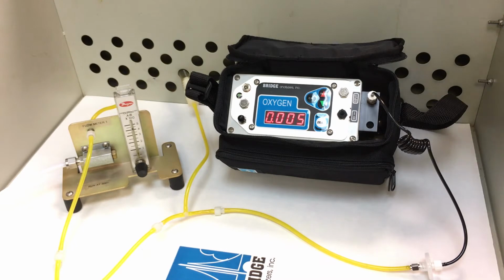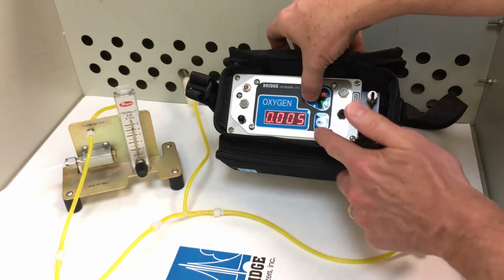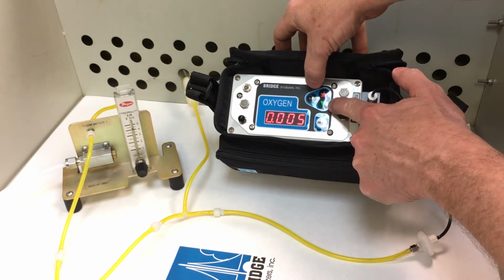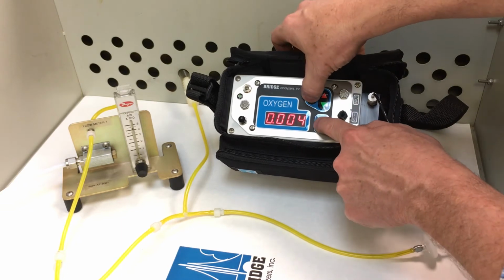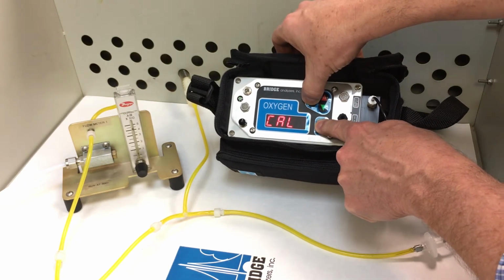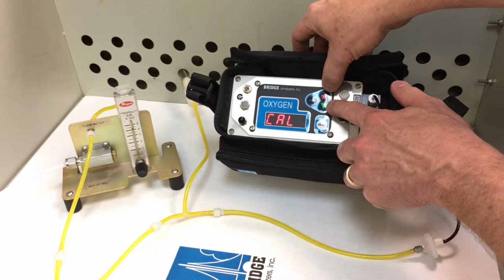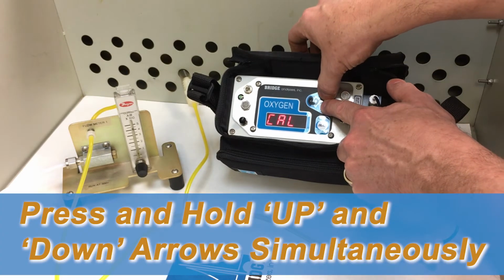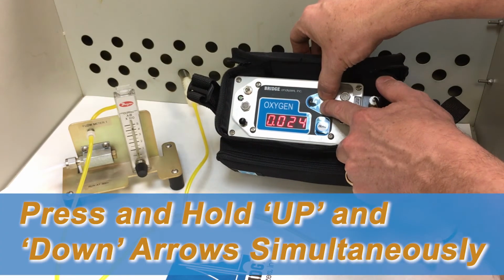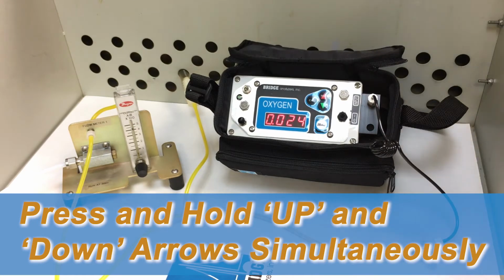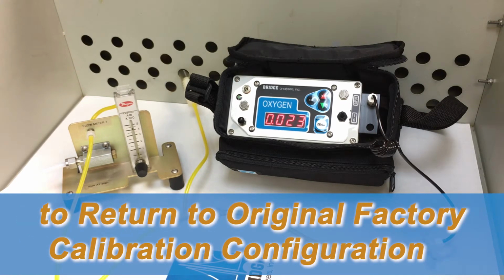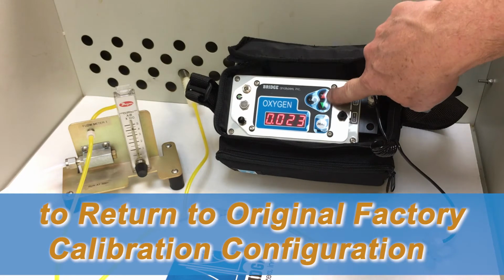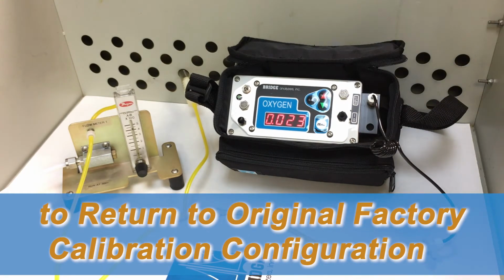The other thing that I wanted to tell you was if I want to go back to factory settings, I go back into continuous run mode, which I'm in, go into cal mode, and press the up and down arrow simultaneously until the cal word goes away. Now I'm back to original factory calibration configuration settings by pressing the up and the down arrow simultaneously.